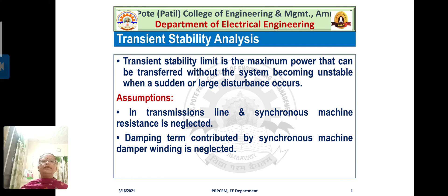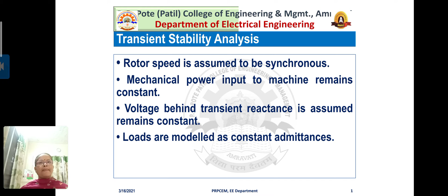Then rotor speed is assumed to be synchronous. Next, mechanical power input to the machine remains constant. And as usual, voltage behind transient reactance is assumed to remain constant. We are familiar with all these statements. And the last one is loads are modeled as constant admittances. Okay, so the bottom line of these assumptions is that whatever the system stability study, we have to represent the synchronous machine by a constant voltage behind reactance. That reactance may be steady state, transient, or subtransient, right?